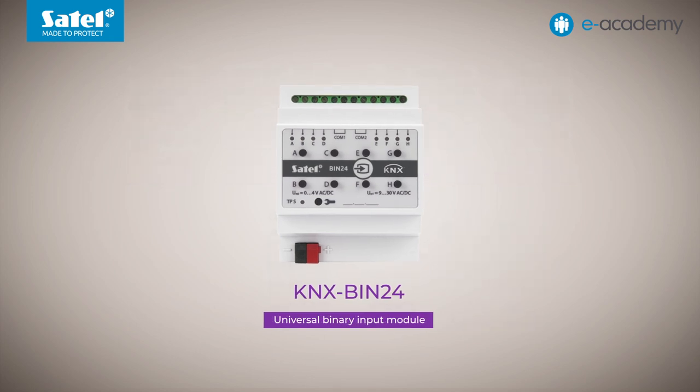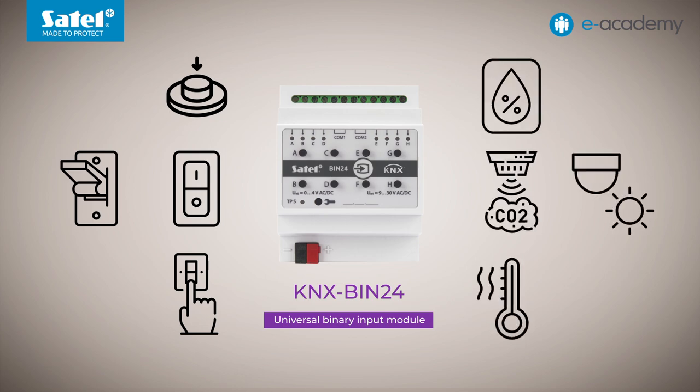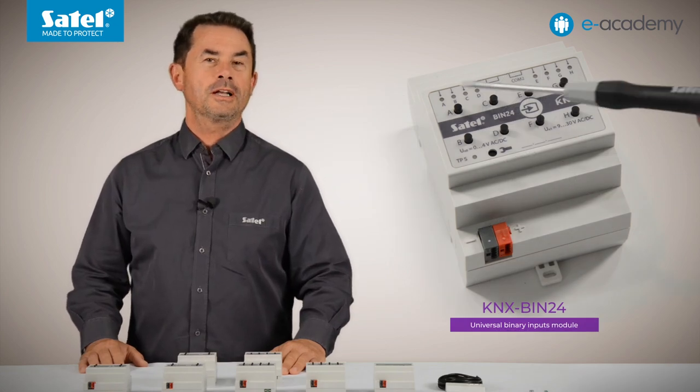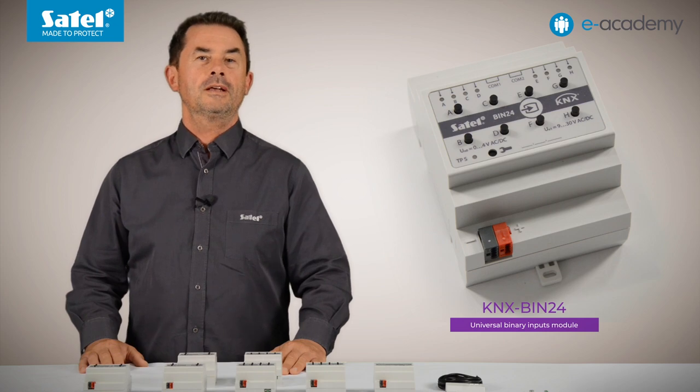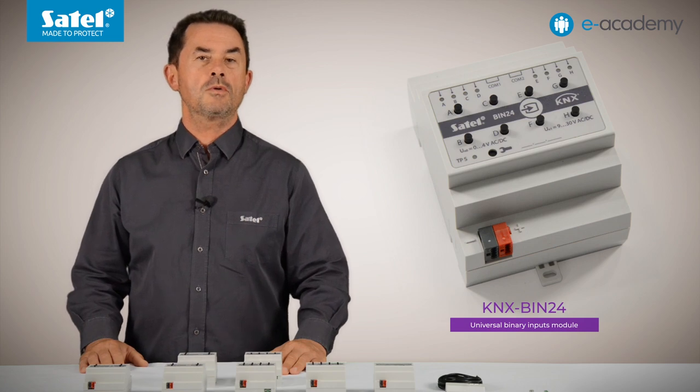Another Satel KNX module is the universal binary input module KNX-BIN24. The device allows electrical signals — specifically voltage signals from 0 to 30 volts AC or DC — to be converted into control telegrams for other KNX devices. These signals can come from buttons used to control light, or be generated by potential contacts of various sensors measuring physical quantities such as light intensity or temperature. The module can also receive telegrams from other KNX devices. The device has four channel groups: physical, virtual, logic and timers. The KNX-BIN24 has 20 function blocks stimulated from any of the module's channels. These blocks can carry out various control functions including switch, edge response, dimmer, shutter control or counter, and can be linked, tied or looped together.